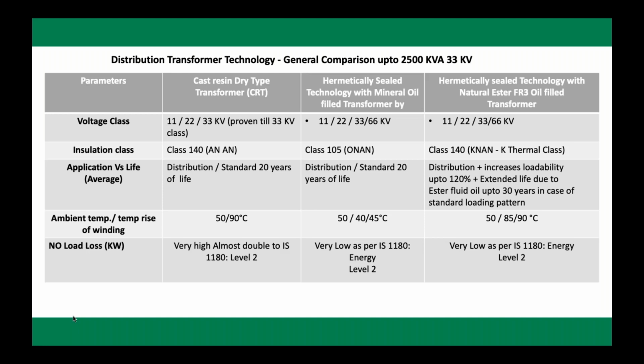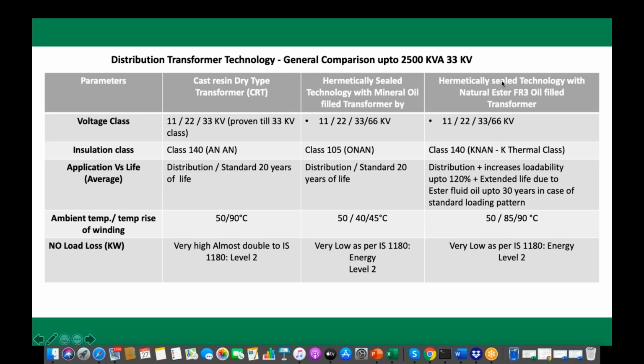And let's speak on some of the limitations. As I said, I like to take some more time on these slides because a lot of questions come after on these slides, and we sometimes skip those slides. So as I said, the dry type transformer up to 33 kV, specially cast resin, you can use. If it is VPI, then up to 11 kV. And when it comes to the oil filled, the O class as well as the K class ester filled, as such there is no limit. You can use it in any voltage class.